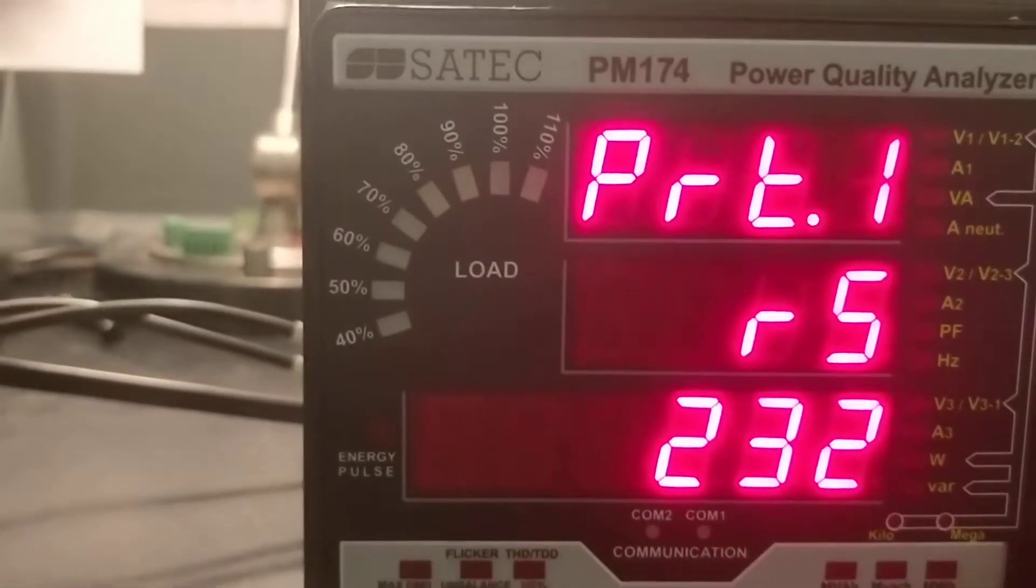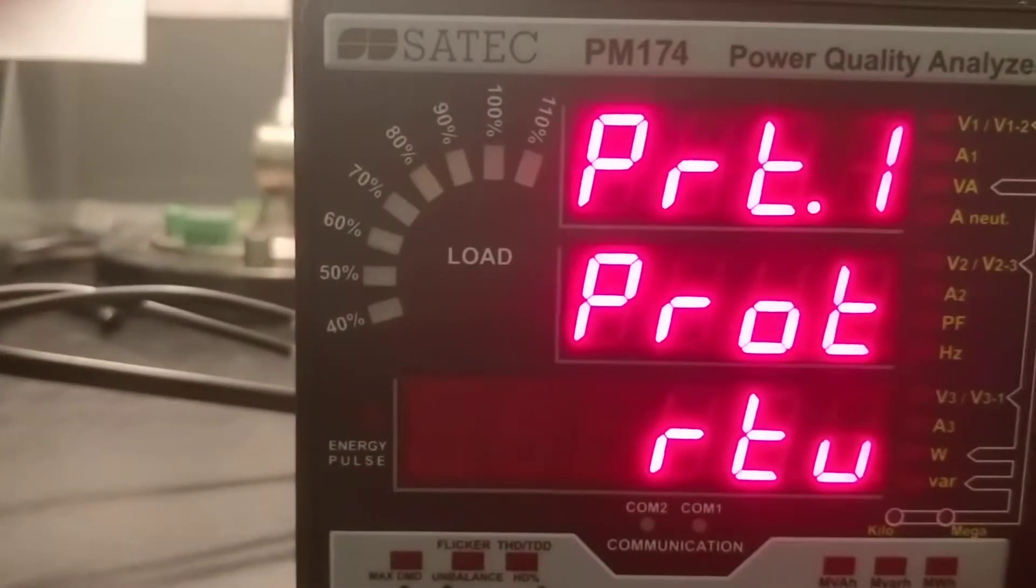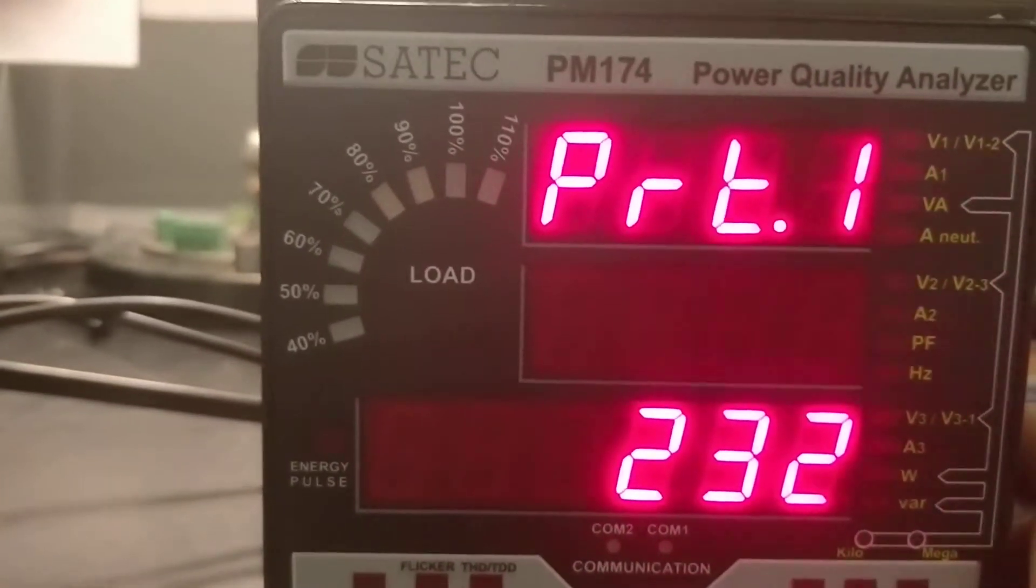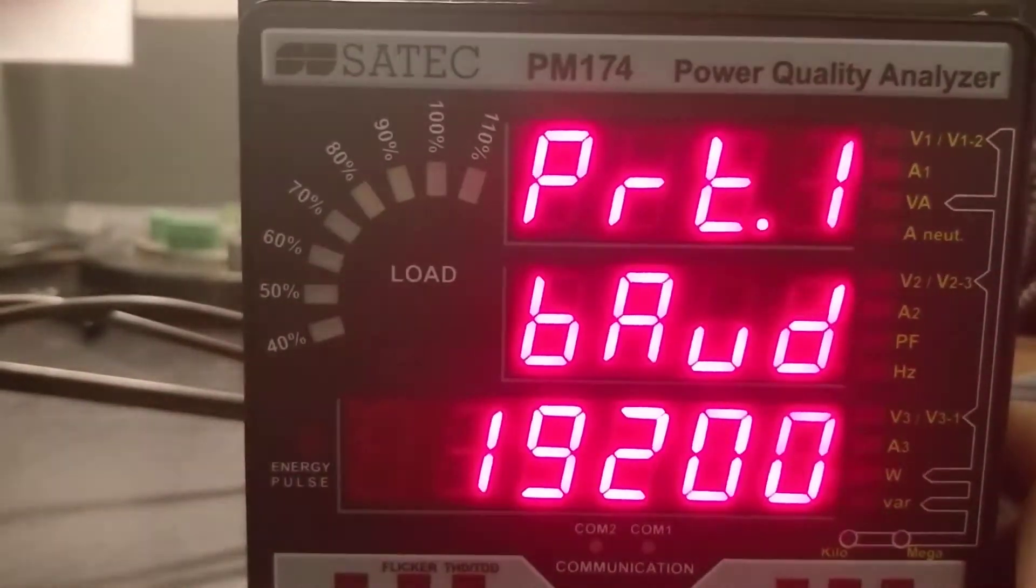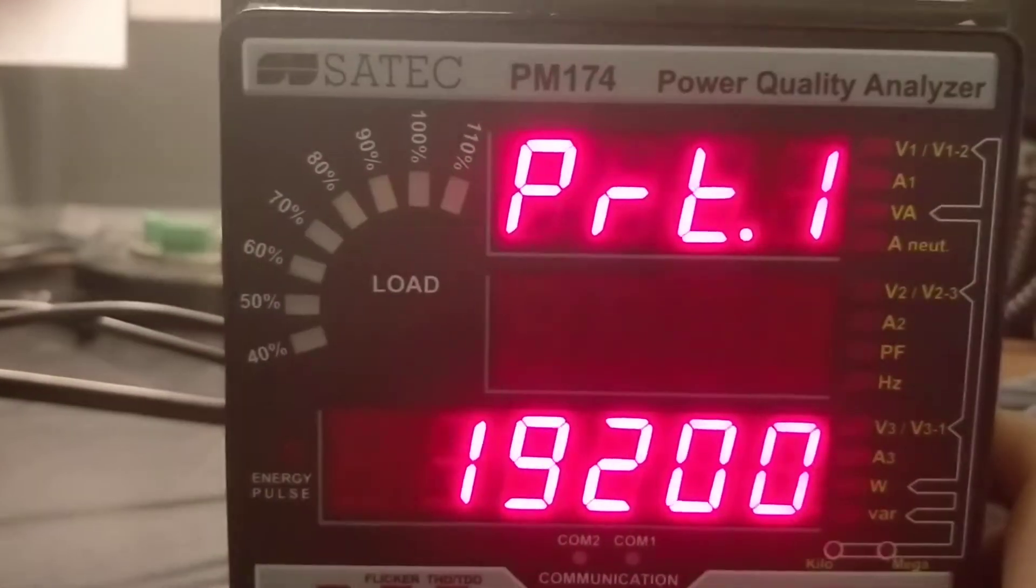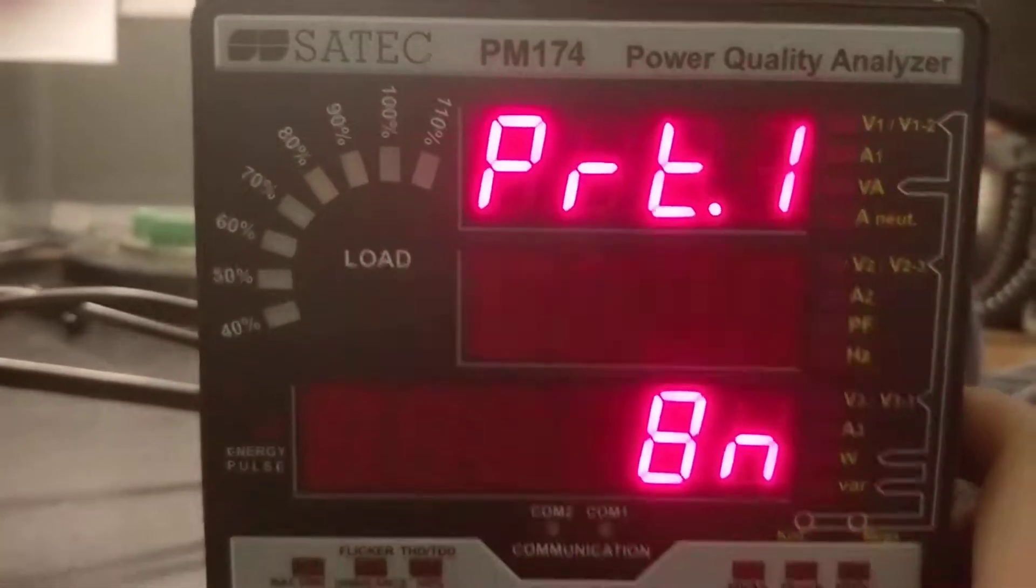You're going to scroll through. Protocol RTU, RS232, address 1, 19200 baud rate, data 8N.